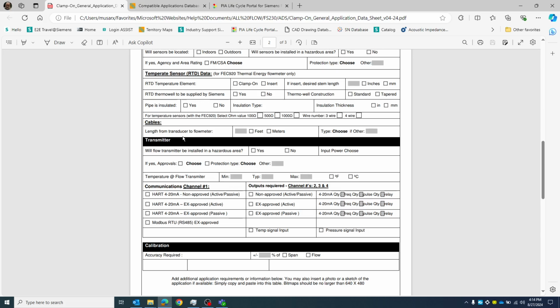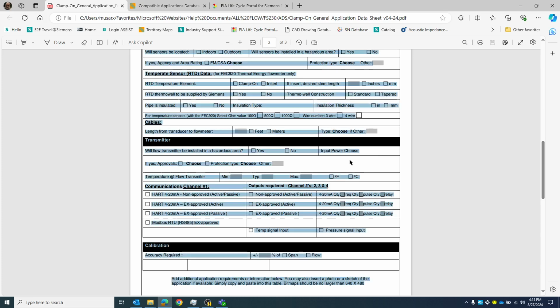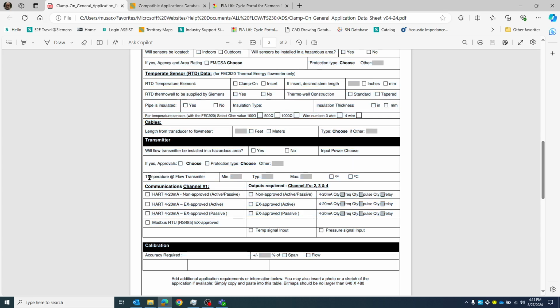We would also need to know if the transmitter will be in a hazardous area, and also what that area classification would be, whether it's Class 1 Div 1 or Class 1 Div 2. That'll help us in determining what the transmitter type should be. If it's an FS230, we don't need to know the input power, as that's field swappable between low power and high power. If it's an FST020, then we need to know if it's standard 110 volts AC, or is it low power AC or DC. As far as the communications, you don't have a choice for an FST020, but you do have a choice if it is an FS230.